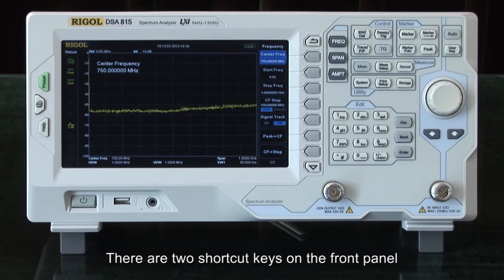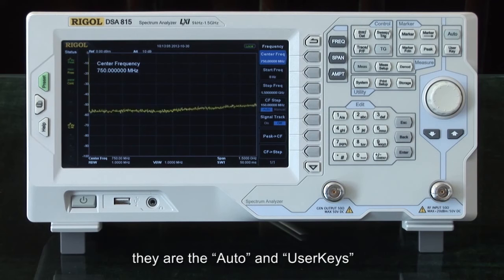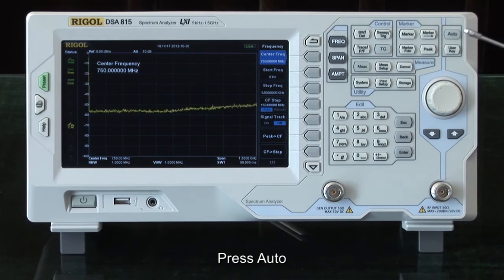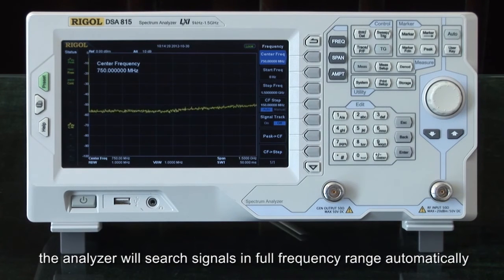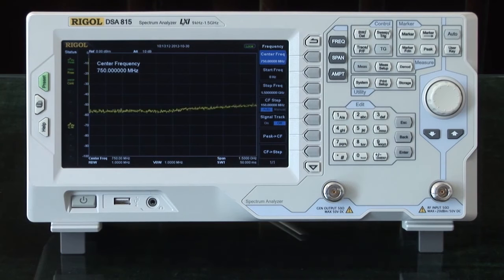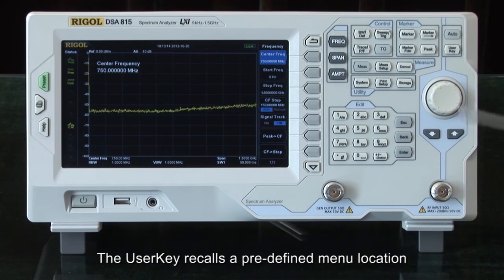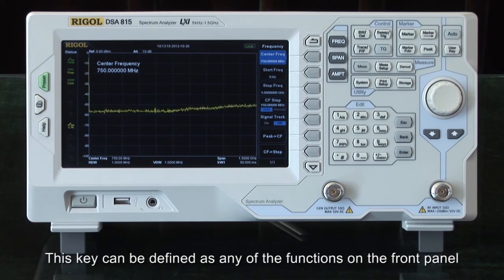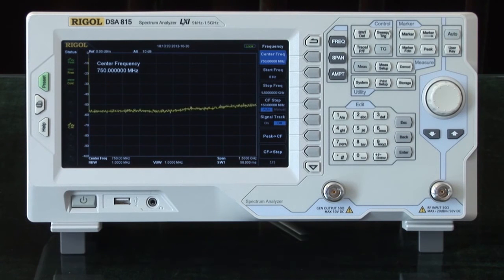There are 2 shortcut keys on the front panel. They are Auto and User key. Pressing Auto, the analyzer will search for signals in a full frequency range automatically. The User key will recall a predefined menu location. This key can be defined as any of the functions on the front panel except the storage function.